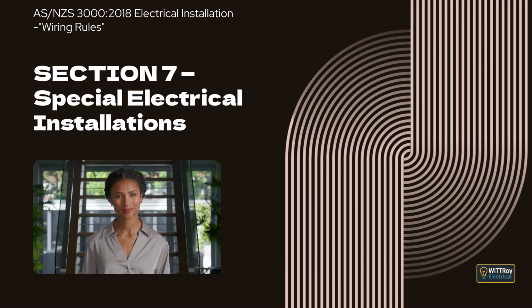Where no wiring system classification is specified, the wiring must be capable of maintaining supply when exposed to fire or mechanical damage, or must maintain supply when exposed to fire while being protected against mechanical damage, either through effective enclosure or suitable location. It also explains that these protection requirements do not apply where wiring is installed in a protected enclosure or location.